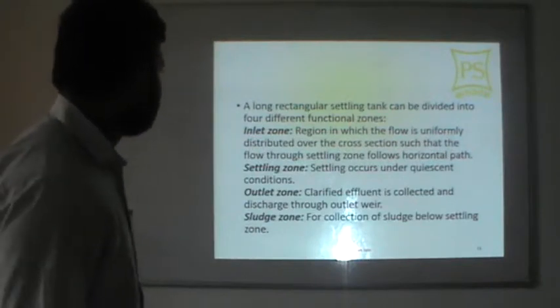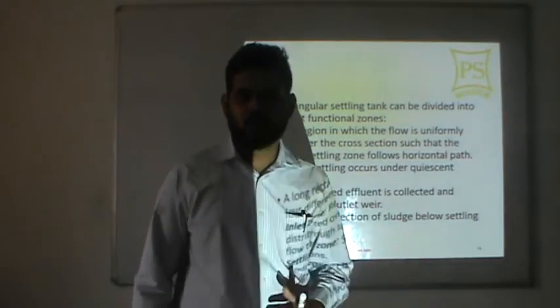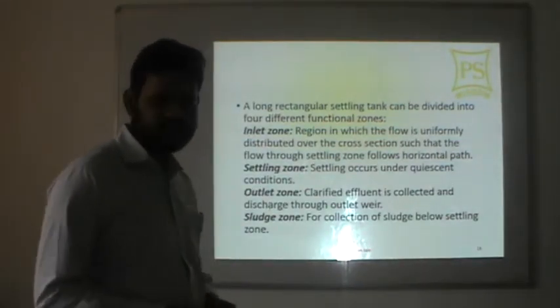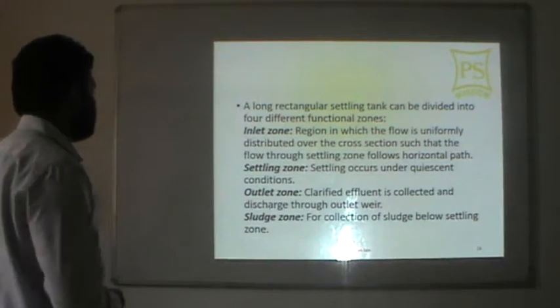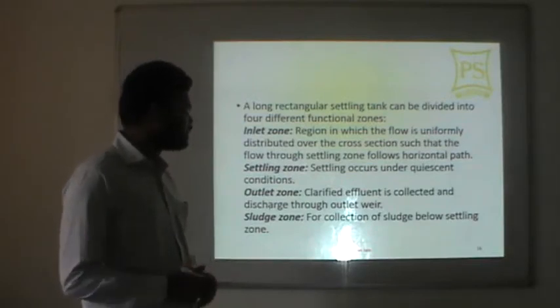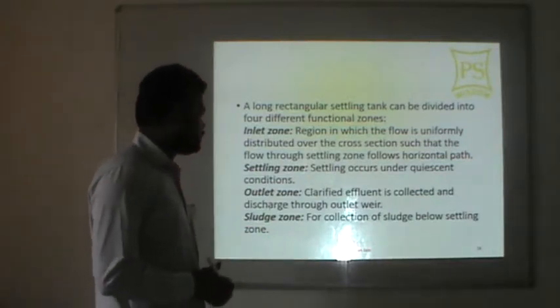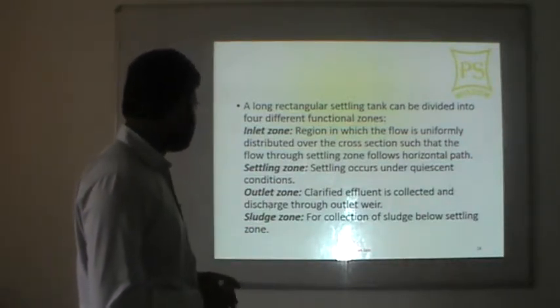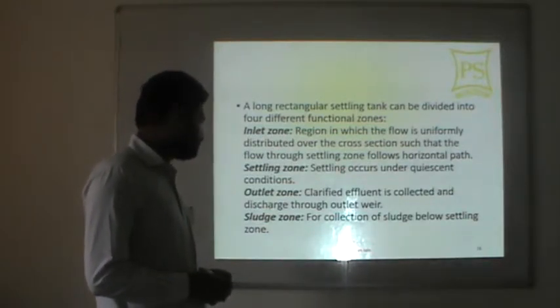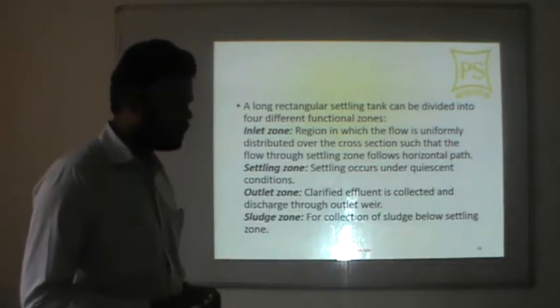A long rectangular settling tank can be divided into four zones. The inlet zone is where flow is uniformly distributed over a cross-section so that flow through the settling zone follows a horizontal path. The settling zone is where settling occurs under quiescent conditions. The outlet zone is where clarified fluid is collected and discharged. The sludge zone is below the settling zone and is for the collection of sludge.